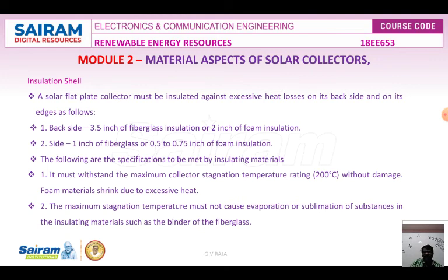The insulating materials must meet the following specifications: they must withstand the maximum collector stagnation temperature of 200 degrees Celsius without damage. Foam materials may shrink due to excessive heat. The maximum stagnation temperature must not cause evaporation or sublimation of substances in the insulating material, such as the binder of fiberglass. Special fiberglass materials are made available for satisfactory outgassing rates.